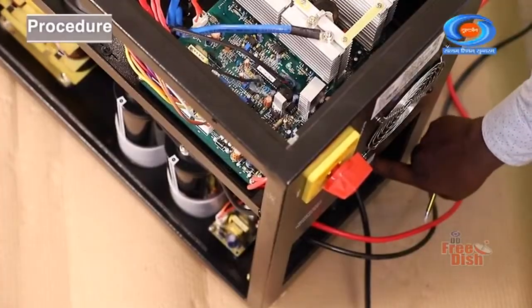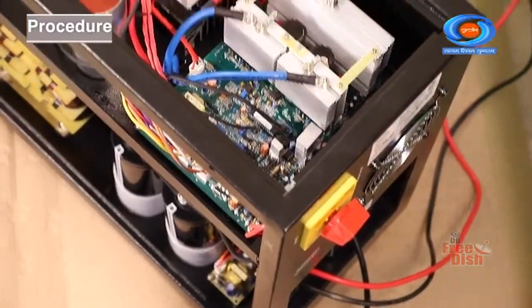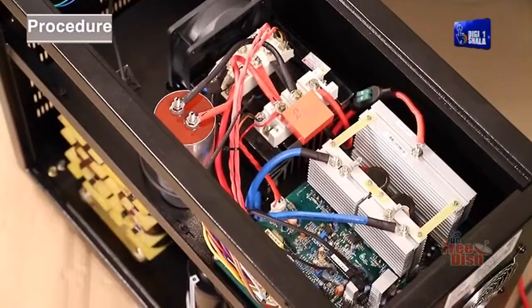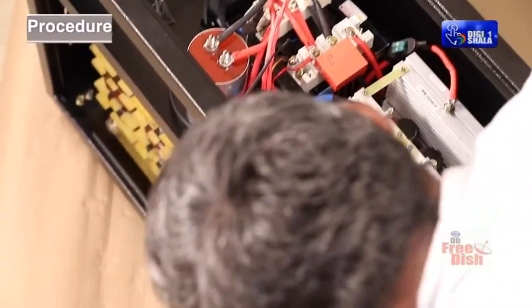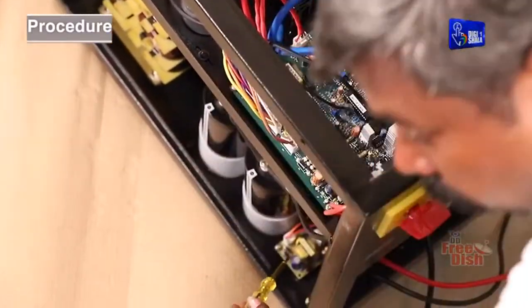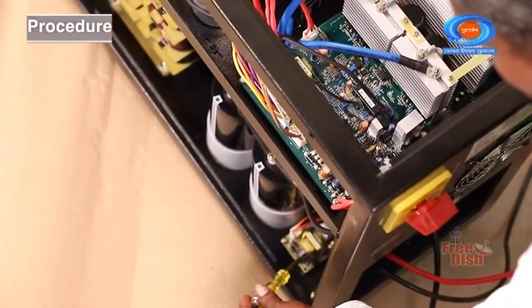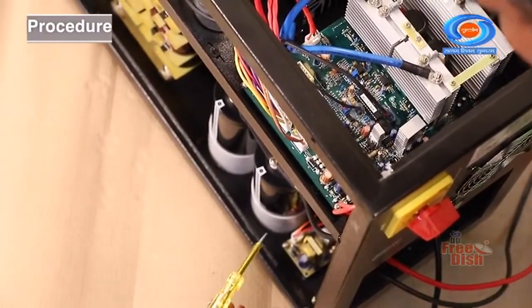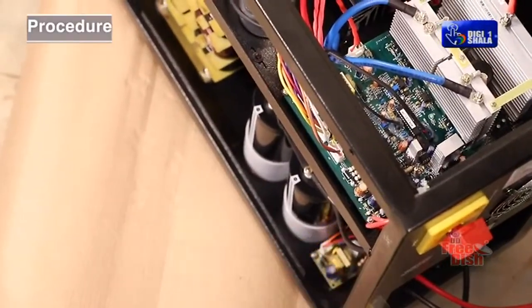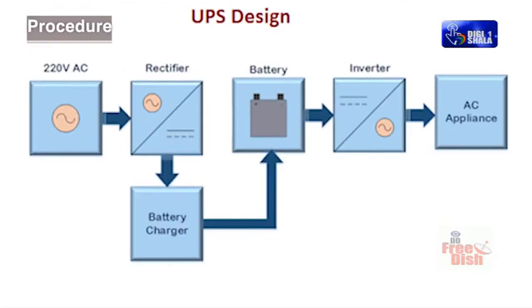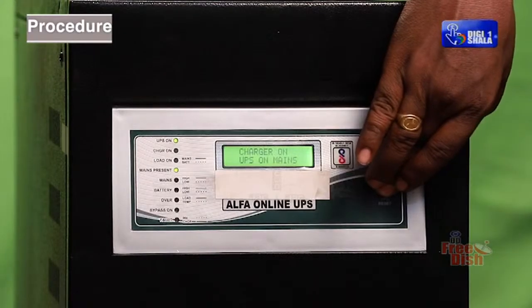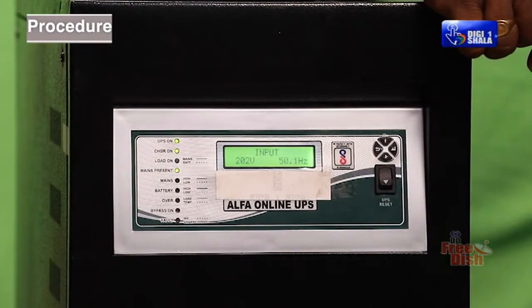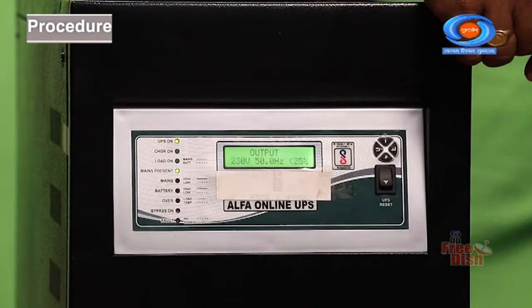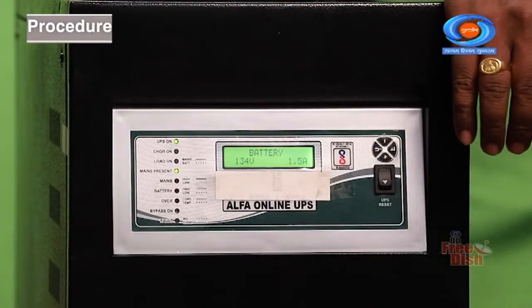Check the condition of the power cord, AC fuse, abnormal voltage, and PCB. Rectify the problem by referring to the troubleshooting sequence block diagram. Press the on-off test silence button for less than 1 second when AC mains supply is available. Observe the operation of the UPS.